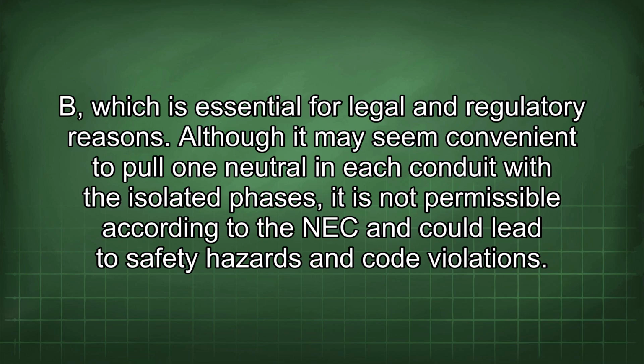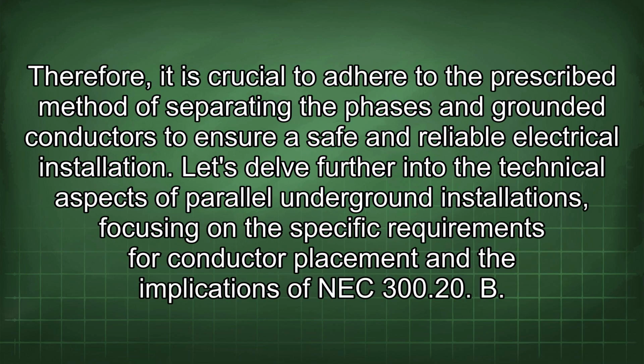Although it may seem convenient to pull one neutral in each conduit with the isolated phases, it is not permissible according to the NEC and could lead to safety hazards and code violations. Therefore, it is crucial to adhere to the prescribed method of separating the phases and grounded conductors to ensure a safe and reliable electrical installation.